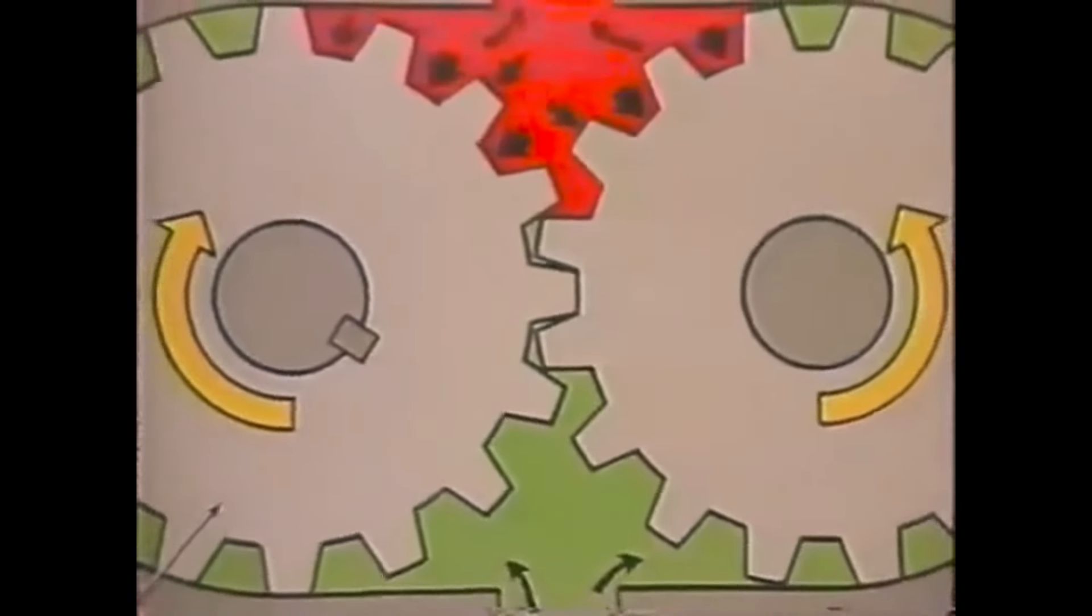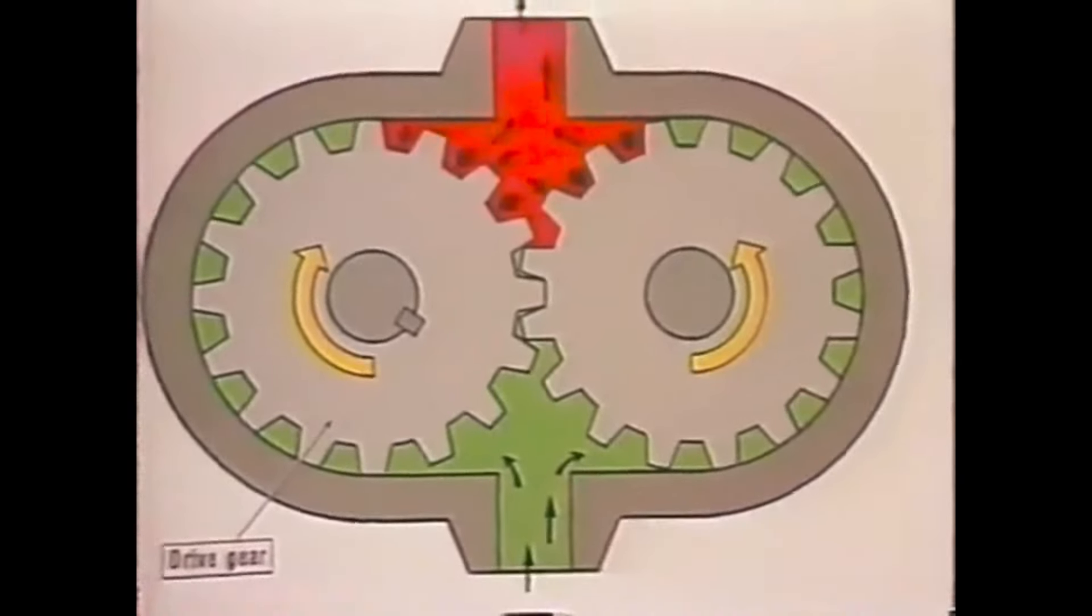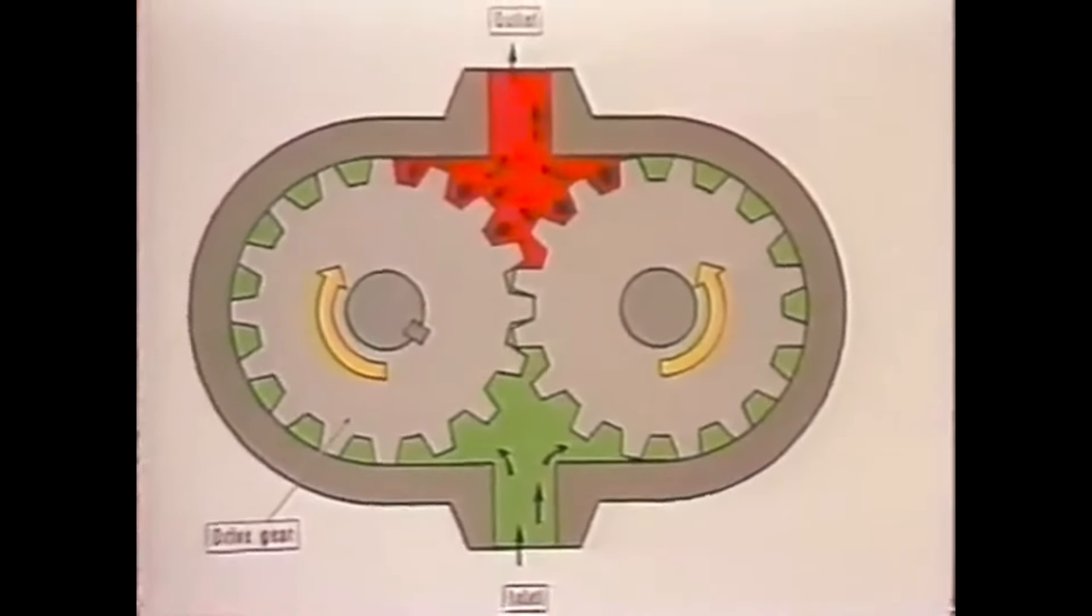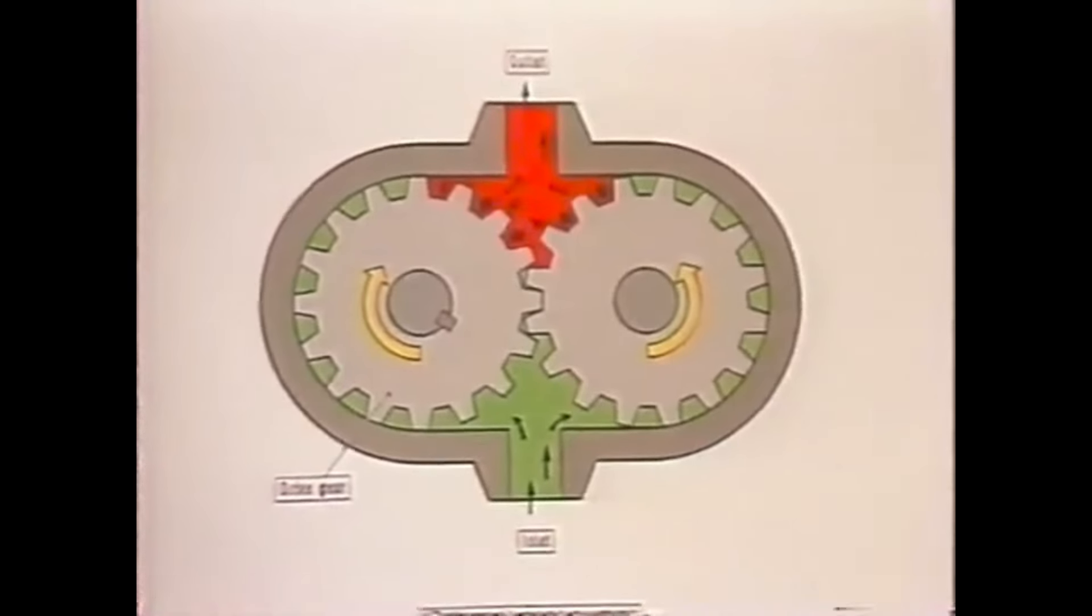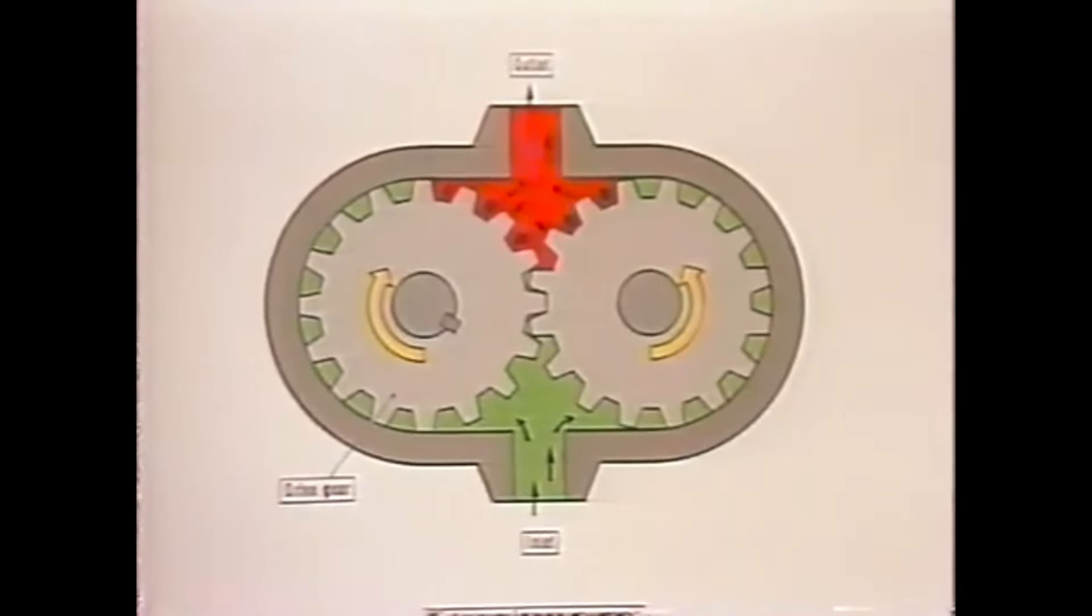This principle applies to all positive displacement pumps, whether they be vane, piston, or gear type. Perhaps the simplest and easiest to understand is a gear pump. One gear driven by the drive shaft meshes and rotates another, called the driven gear. Both are contained within a close-fitting housing. A partial vacuum is created at the inlet as the gear teeth unmesh, and fluid flows in to fill the void. Then the fluid is carried around the gears to the pump outlet. As the teeth go back into mesh, oil is forced out through the outlet port.